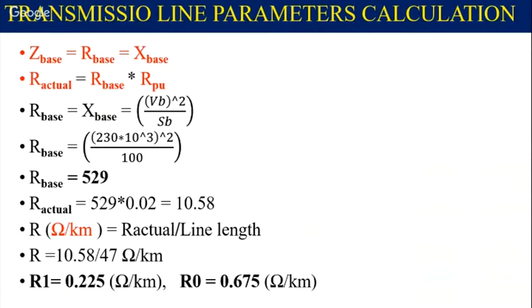Now we want to calculate the resistance of the line. You know that Z base is equal to R base, which is also equal to X base. R actual is R base into per unit. R base is base voltage square upon base MVA. With that, the base resistance is 529 and the actual resistance is per unit into base, which comes to 10.58. Now we want it in ohms per kilometer, so it is divided by the 47 kilometers that we calculated. So R1 is the actual value of the transmission line resistance in ohms per kilometer, and the zero sequence resistance is 3 times the positive sequence value.